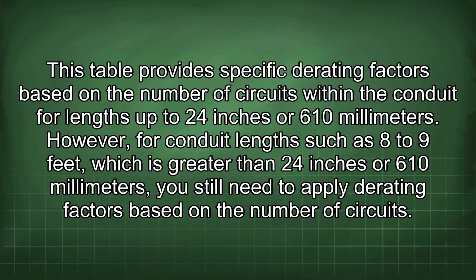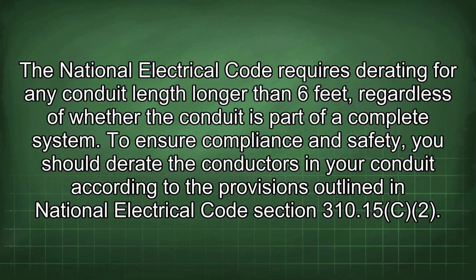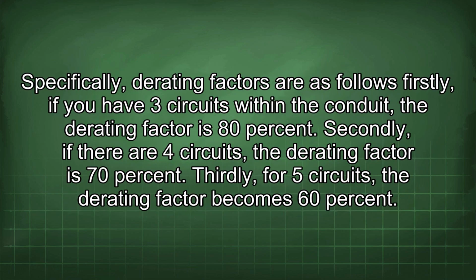However, for conduit lengths such as 8 to 9 feet, which is greater than 24 inches or 610 millimeters, you still need to apply derating factors based on the number of circuits. The National Electrical Code requires derating for any conduit length longer than 6 feet, regardless of whether the conduit is part of a complete system. To ensure compliance and safety, you should derate the conductors in your conduit according to the provisions outlined in National Electrical Code Section 310.15(C)(2). Specifically, derating factors are as follows.